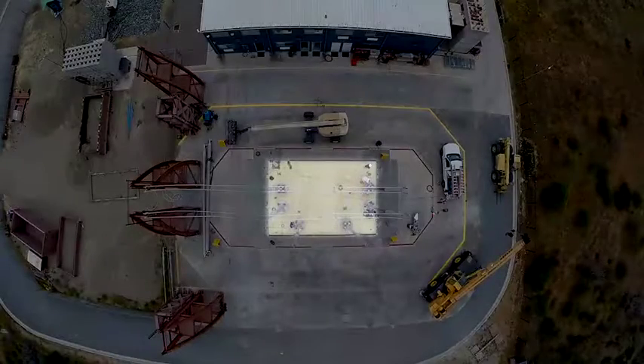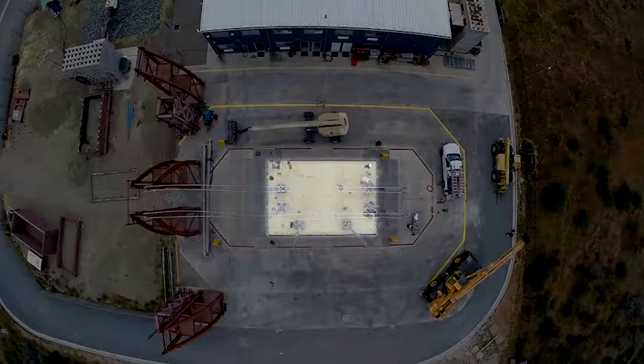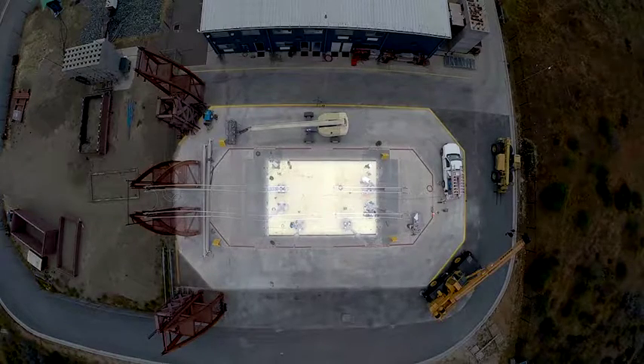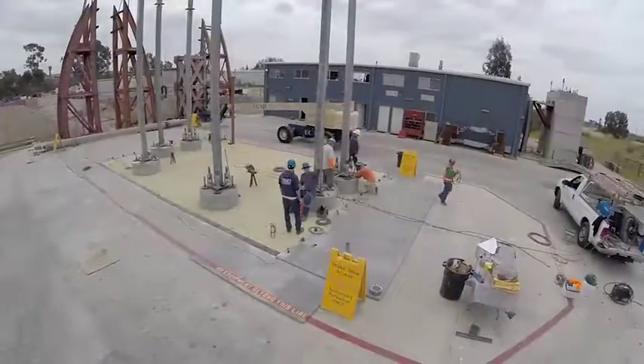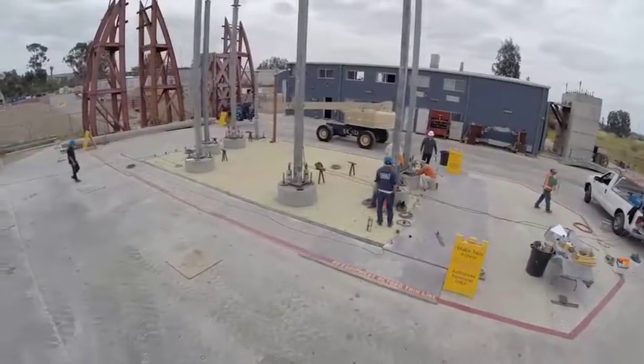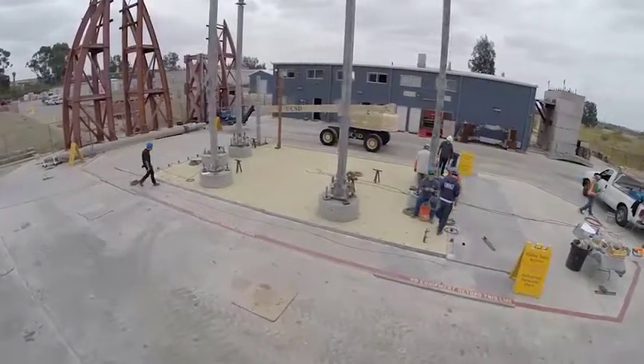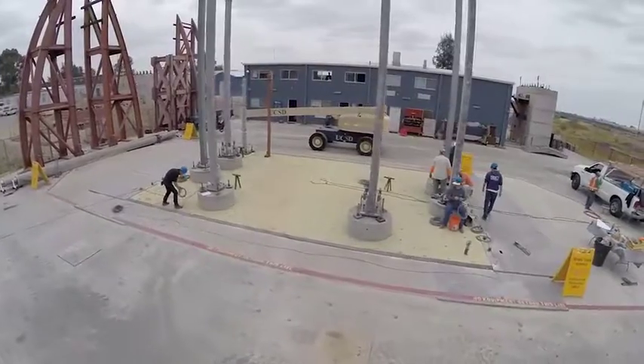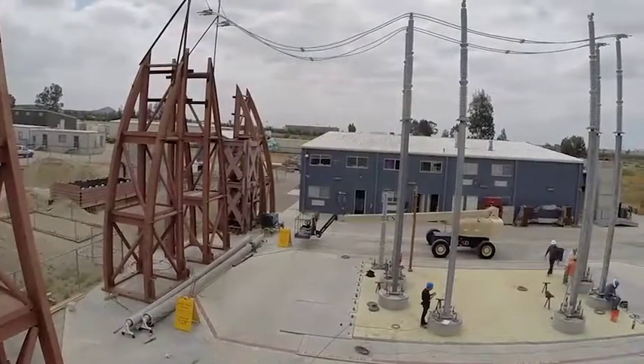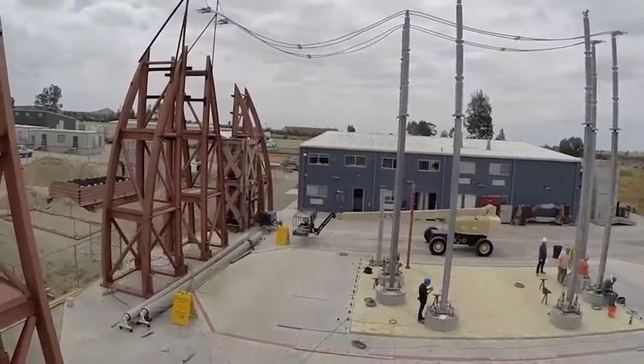The platen, which is the part of the shake table that moves, is surrounded by a reinforced concrete reaction mass. Installed here on the table is a full-scale electrical substation consisting of poles and insulators, some of which are equipped with spring dampers at the base supporting 500 kilovolt transmission lines.